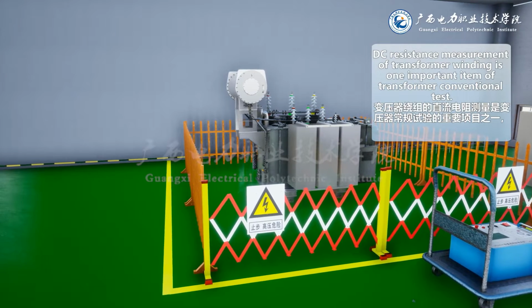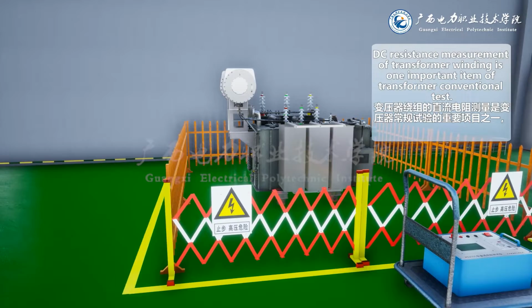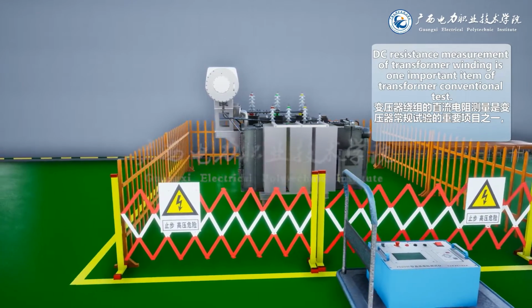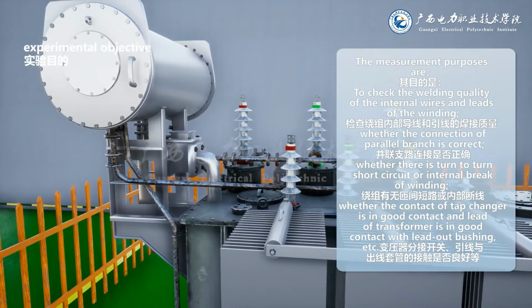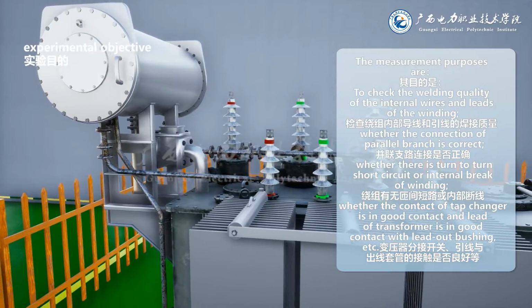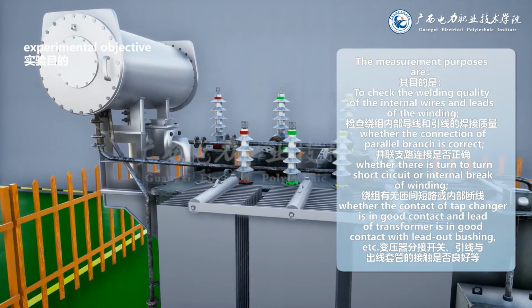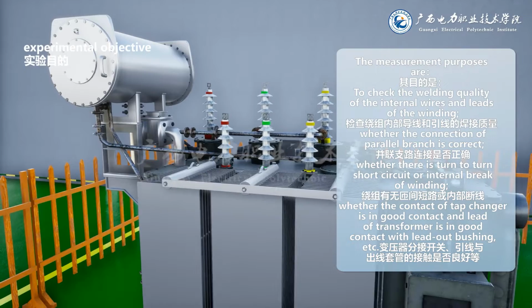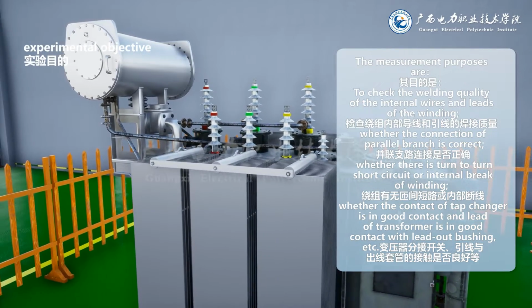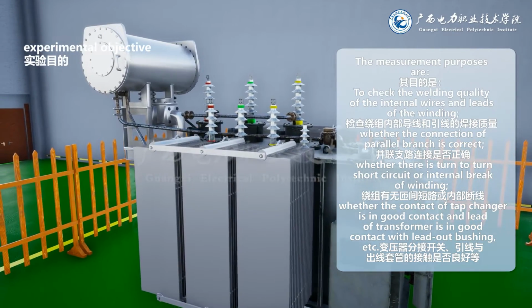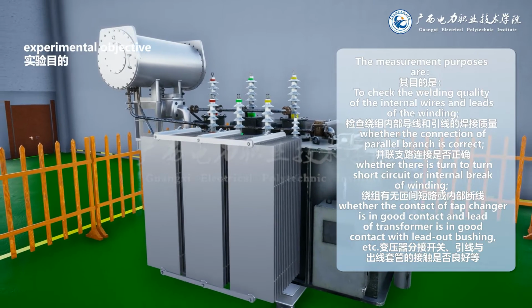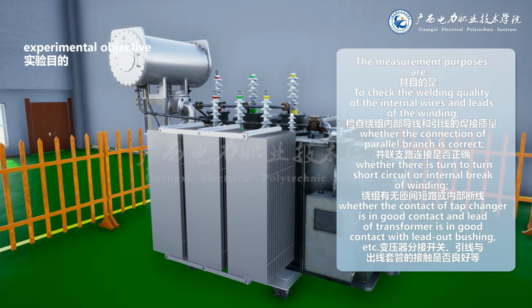DC resistance measurement of transformer winding is one important item of transformer conventional test. The measurement purposes are to check the welding quality of the internal wires and leads of the winding, whether the connection of parallel branch is correct, whether there is turn-to-turn short circuit or internal break of winding, whether the contact of tap changer is in good contact and lead of transformer is in good contact with lead-out bushing, etc.